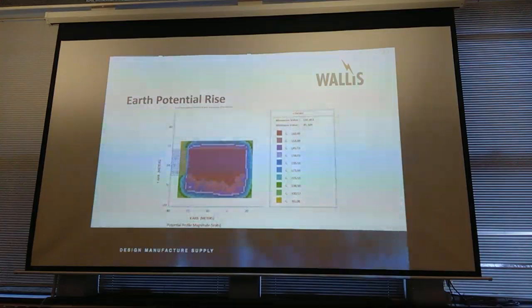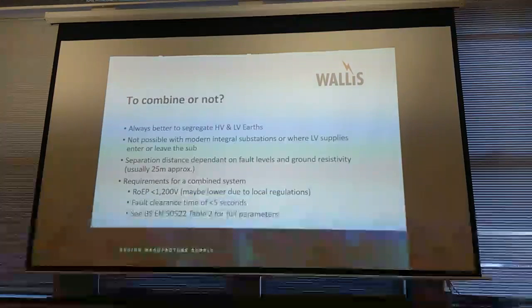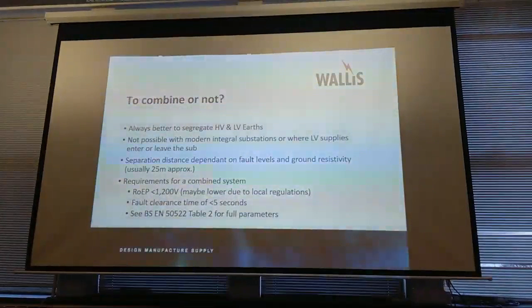If you're on the end of a very long cable feed, 2, 3, 4 kilometres of cable impedance, then you will get a hell of an amount of current going to the earth system as opposed to what's going up the cable sheath, if that makes sense. Again, and forgive me, I could talk about this for quite some time as well.